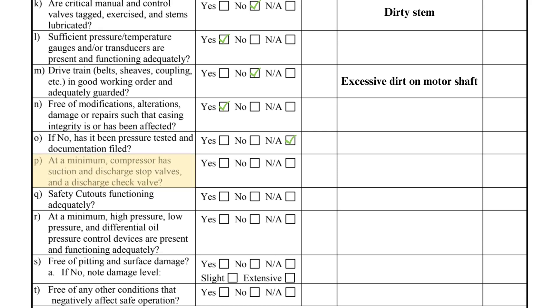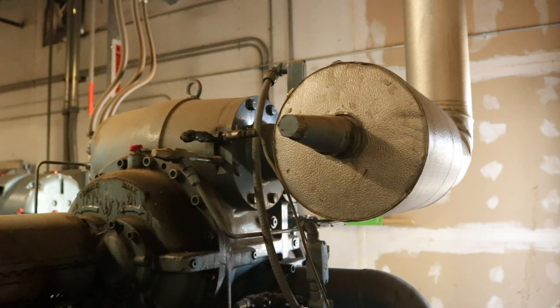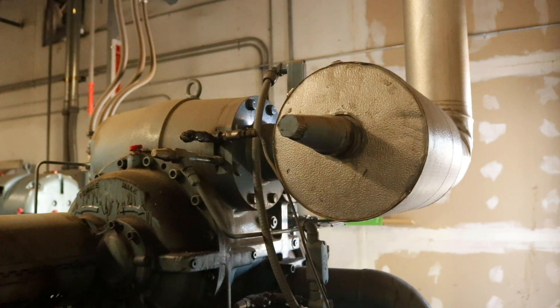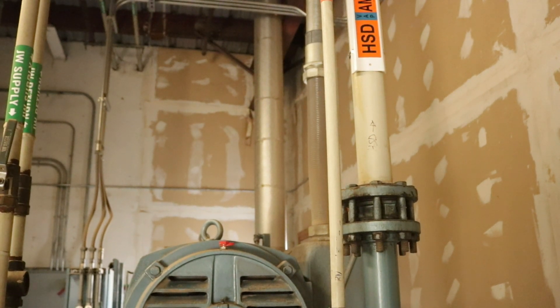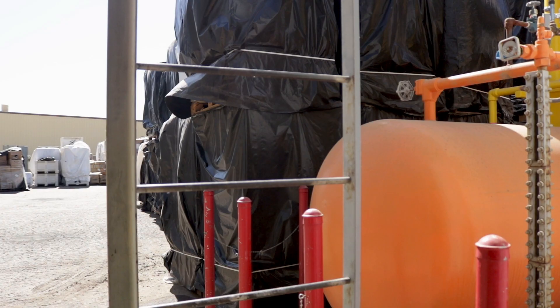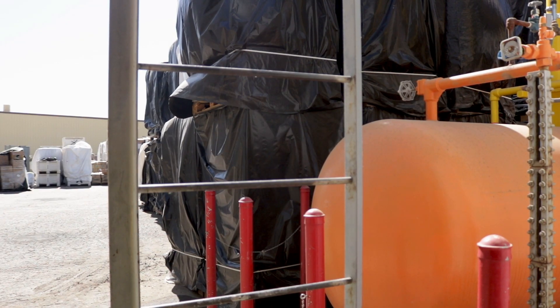Item P asks if the compressors at minimum have suction and discharge stop valves and a discharge check valve. Most compressors come equipped with these valves from the manufacturer, so it is unusual for these valves to be lacking. However, the discharge isolation valve on this compressor is not located near the unit and requires climbing a ladder to the roof in order to access the valve, which is not ideal.